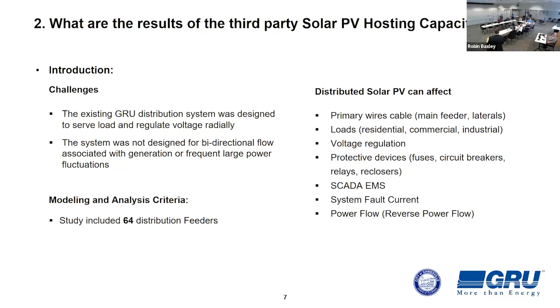Okay. Now, as far as developing the model, we worked with a third-party vendor and gave them the information that we use on our circuits, such as the loading criteria for each distribution circuit. What is the maximum capacity of each circuit based on the size of the conductors? We also gave voltage and imbalance issues for those circuits for various times of day, because when the system's loaded heavily during the hot part of the day or a cold part of winter, the voltage is going to be down, whereas at night the voltage is going to be higher because the system is more lightly loaded in most scenarios.